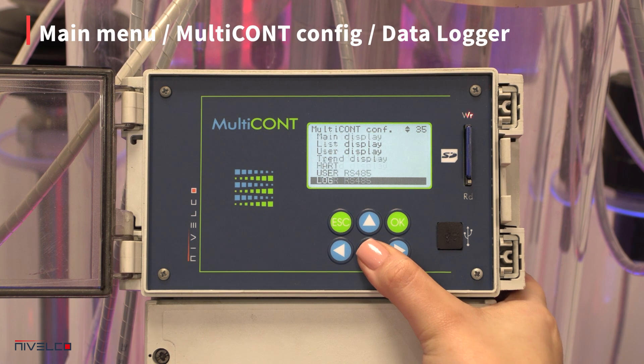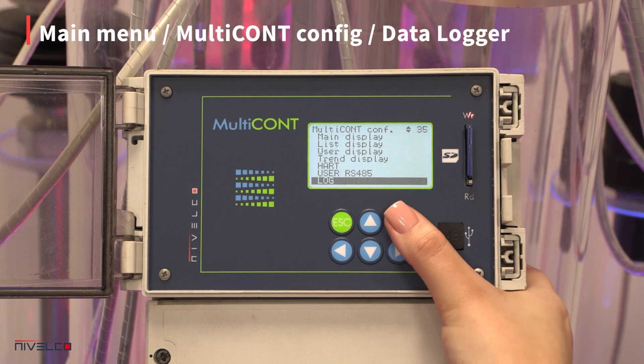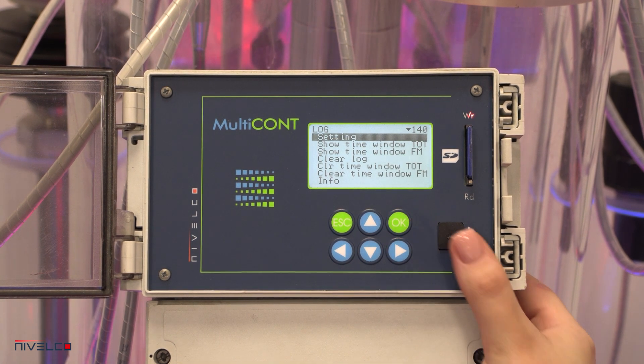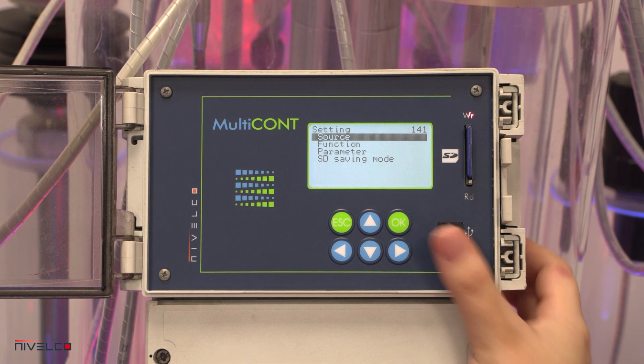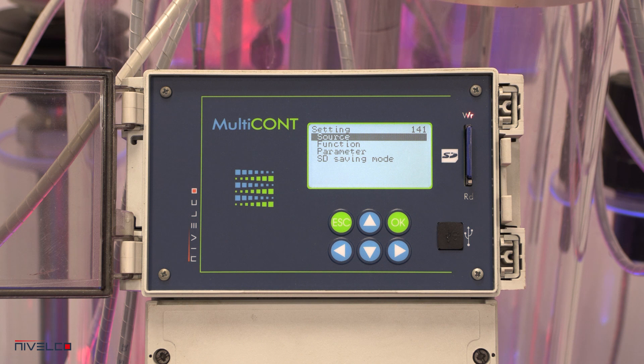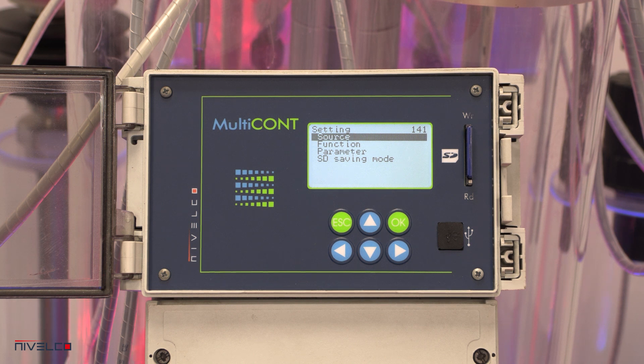The Multicont's data logger logs data in flash memory, but the PED, PRD, PEN, and PRN types can write logs to an SD card. The unit logs the ID of the transmitters, the primary value, and three additional values. Time-controlled logging stores entries after a specified amount of time, while event-controlled logging stores entries when a set condition is met.